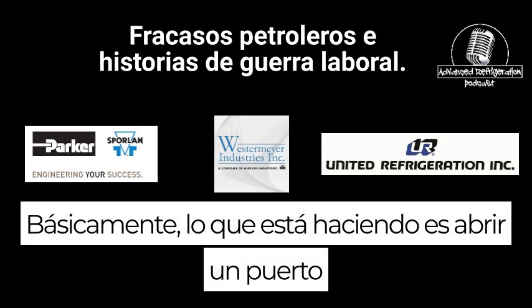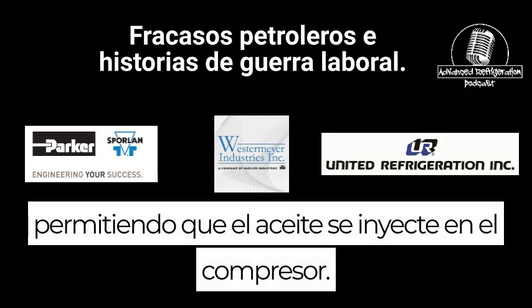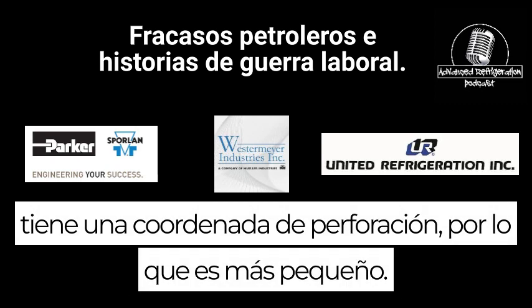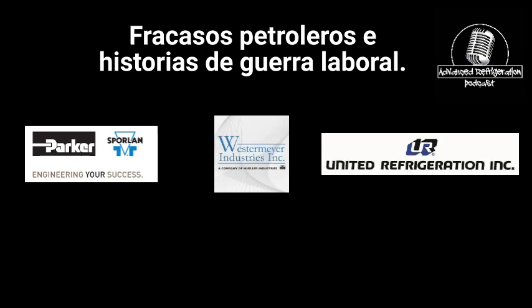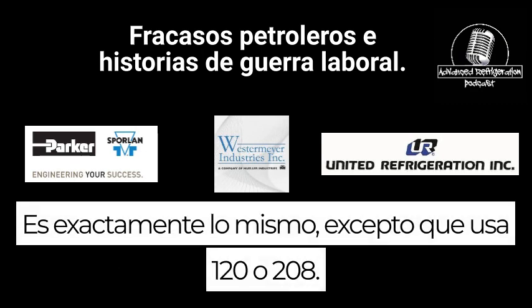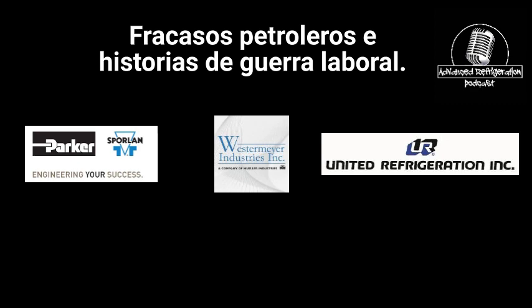Basically what it's doing is opening a ported solenoid valve inside of the oil float that is allowing oil to inject into the compressor. Now it's not full flow 1/4 inch. It has a drill port in it, so it's smaller. Same thing with an OMC. It's the exact same, except it's using 120 or 208. Usually they either work or they don't.